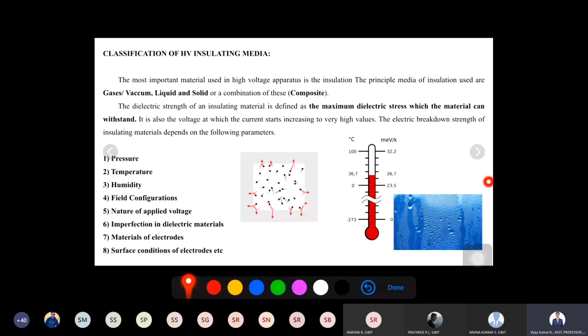And next comes humidity. Humidity is also a very important point, because even a small moisture content, say 0.0001%, present inside any insulating media will affect it. Instead of withstanding 1000 kilovolts, it may break down at only 100 volts, because the current will take a path through that moisture content and break down. That's the reason humidity is also one of the parameters here.